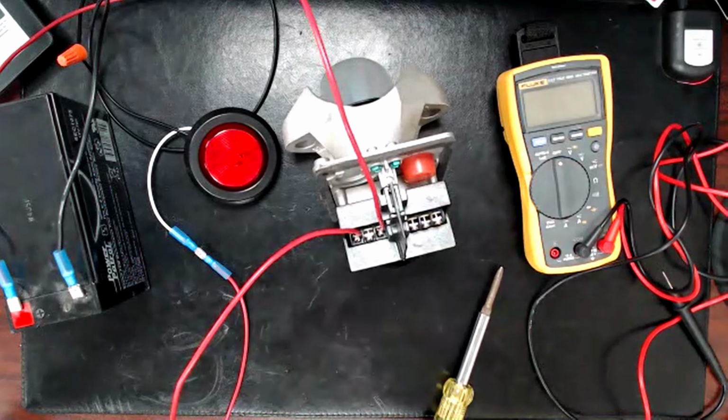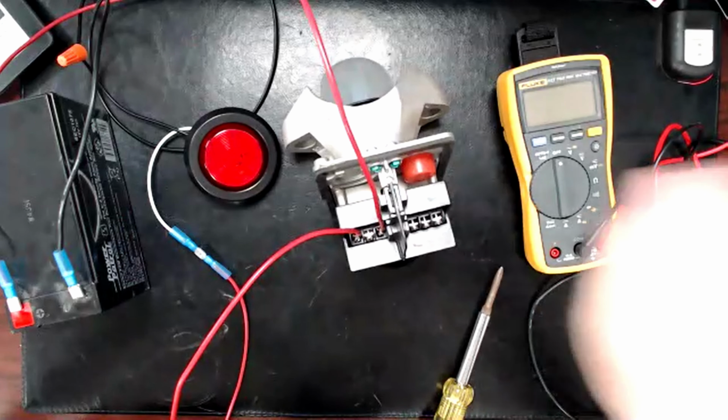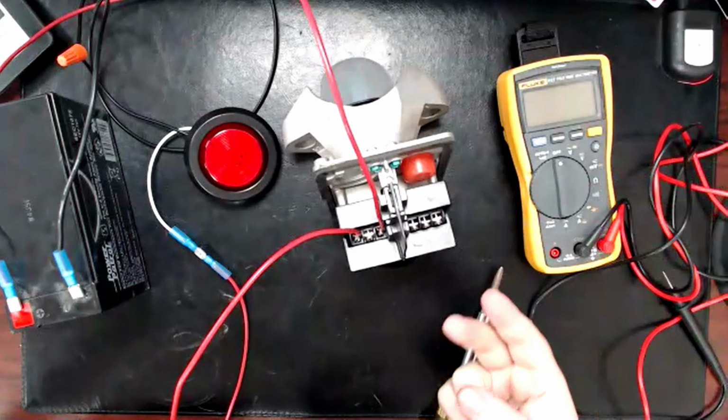For anyone that's not sure what series and parallel is, that would be like if you have 2 sets of wires. So you have your aux power wire coming from your dialer and it lands under the terminal and it has its red and black. And then you have your wire coming over from powering your bell and it has the red and black there. What I'm saying to do parallel is where you put both red wires under the positive terminal and both black wires under the negative terminal, so that if anything happens to either wire, the other part of the system still functions properly.